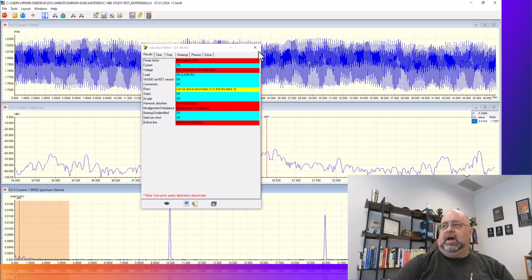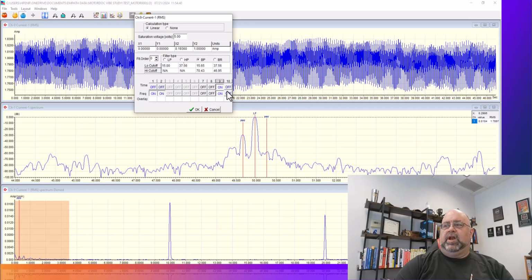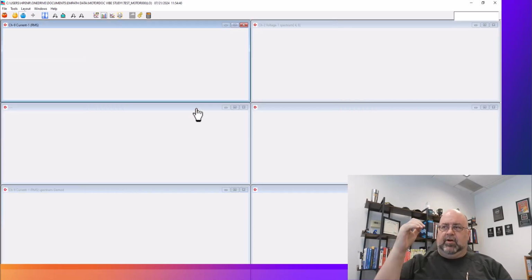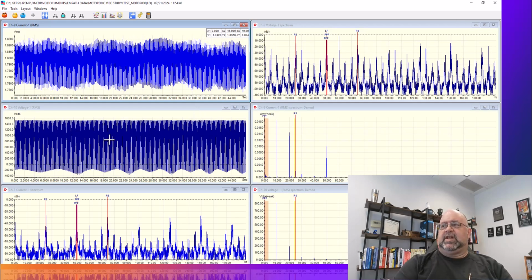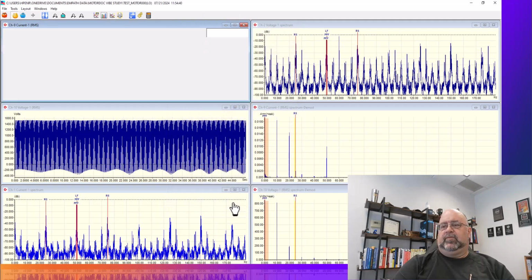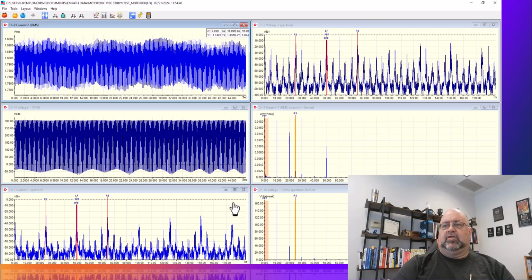Okay. And then once we've noticed the problem with the voltage, first off, let's go ahead and open up the voltage signature as well. So we're going to look at both voltage and current. I want to see what it looks like here, and then I'm going to correct it. Okay, so it's telling me voltage is pretty darn high, of course. It's up significantly high. So let's go ahead and we will then also change our PT ratio to 0.2. That looks closer. That looks about right.